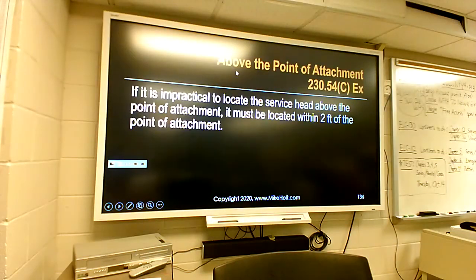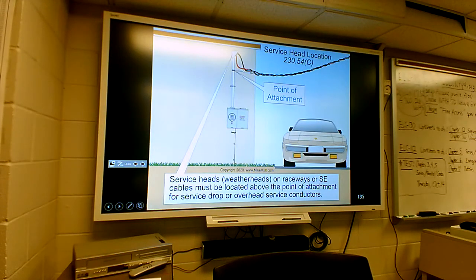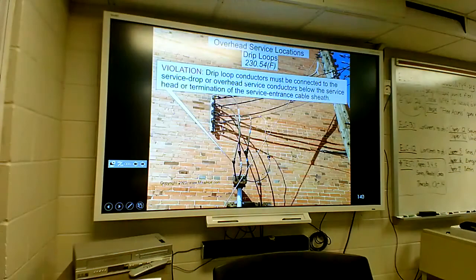Let's back up. When you have a loop like this where it's going down, it's going to drain and drip this way to where the next one is a violation, because at your connections there, the rain can actually drip into the weather head. So you can't have that. That won't pass, because it doesn't have a drip leg that's below this. Drip loop conductors must be connected to the service drop below the service head or termination. And so it can just naturally drip.